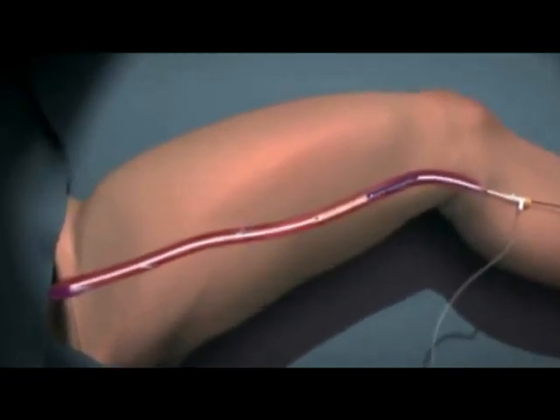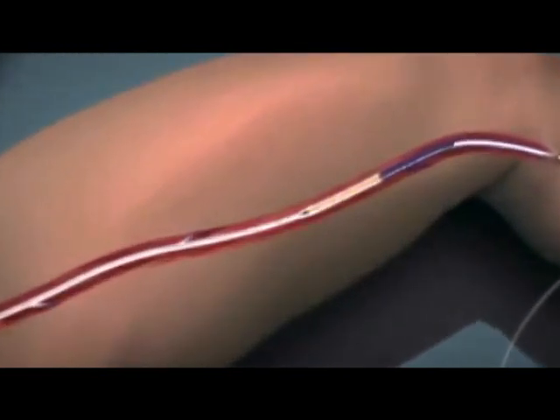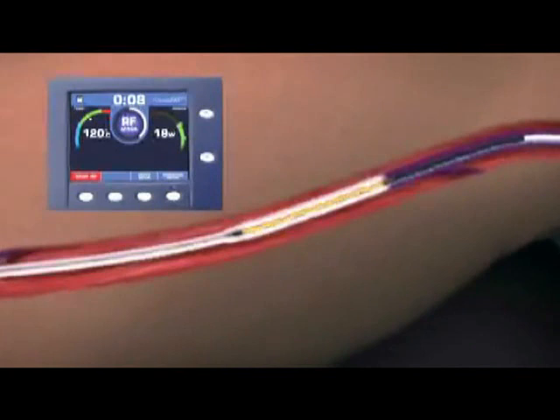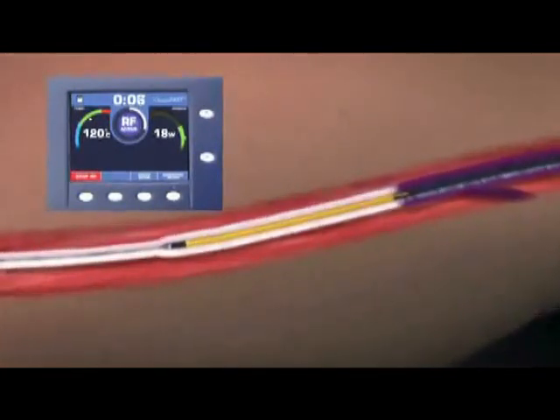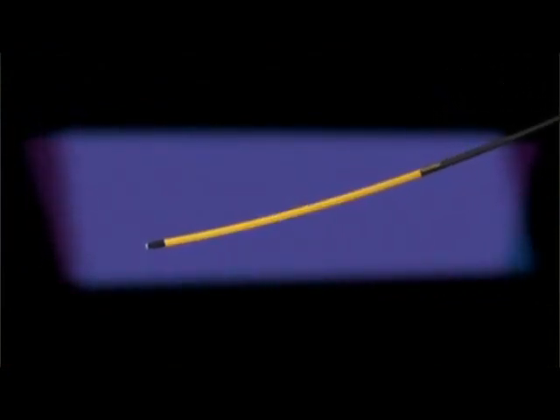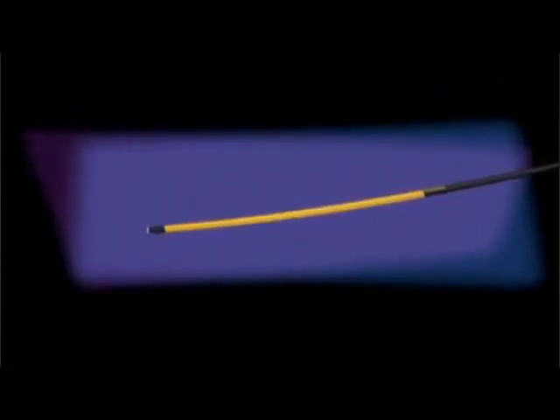Fully compatible with existing VNUS RFG2 generators after a software upgrade, the closure fast catheter monitors treatment parameters in real time and delivers optimal therapeutic power through the system's controlled feedback mechanism. Now, with the new VNUS ClosureFast catheter, the speed and simplicity of endovenous RF procedures in the office and hospital may be significantly enhanced over existing therapies.